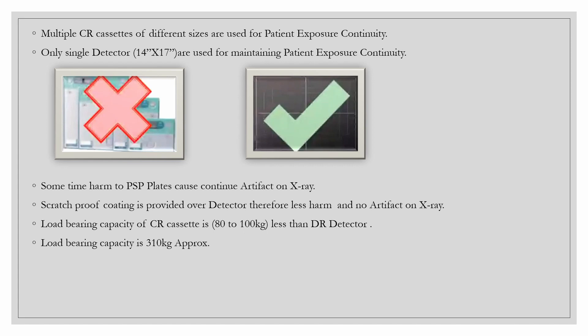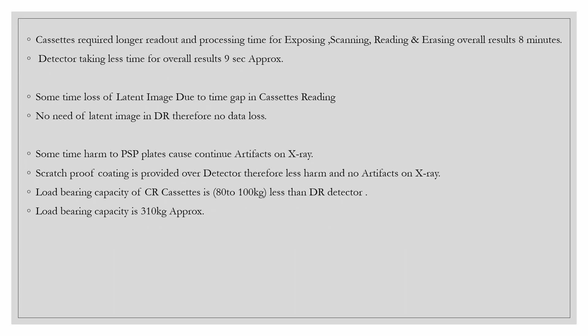Sometimes harm to the PSP plate causes continuous artifacts on X-ray. In DR, a scratch-proof coating on the detector provides less harm and no artifacts. The load-bearing capacity of CR cassettes is around 80 to 100 kg, which is less than the DR detector's load-bearing capacity of around 300 kg — a big difference. CR cassettes also require longer readout and processing time for exposing, scanning, reading, and erasing — around 8 minutes.